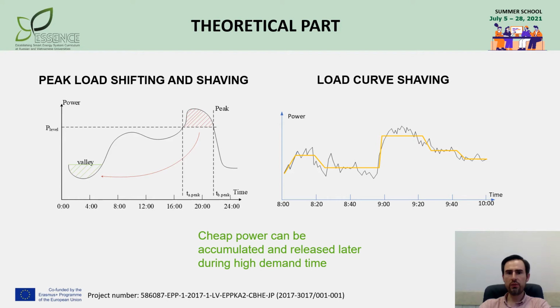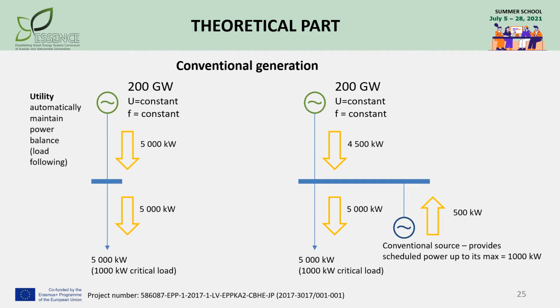Thus, it's wise to define an appropriate combination of different distributed sources to achieve microgrid goals. Well, let's discuss specifics of the use of different distributed resources. We start with conventional generators with controlled output. If we consider a standard distribution grid with no distributed resources, the load is supplied by the utility grid. But if we lose the grid connection, the load is fully de-energized.